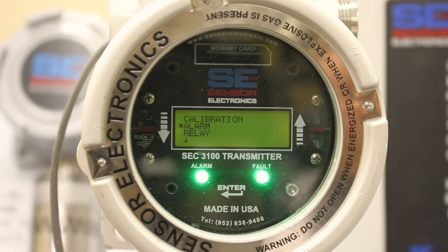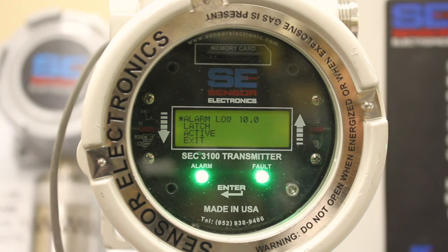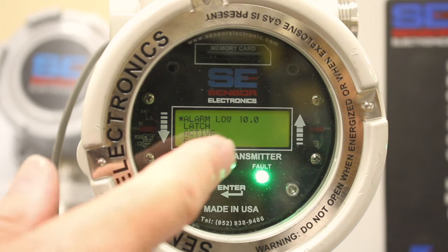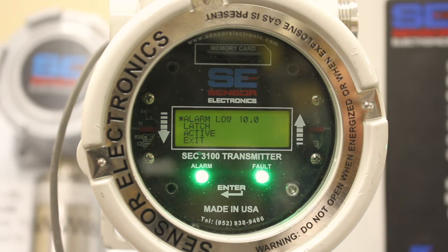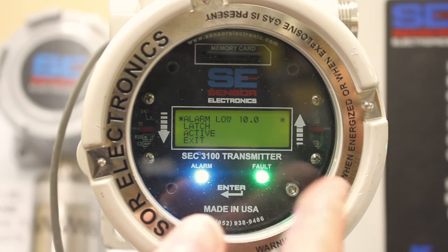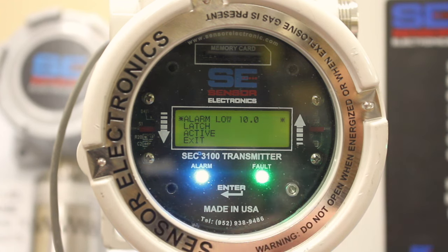The next one is titled Alarm. To enter that one, we have 3 different alarm relays in the transmitter head, and this allows you to program the relays for the alarm set points. So right now the low alarm is programmed for 10%, and to change it you would just select Enter, get the cursor there, and then you can use the up-down arrows to change the alarm levels. And once you select it, you've changed it.